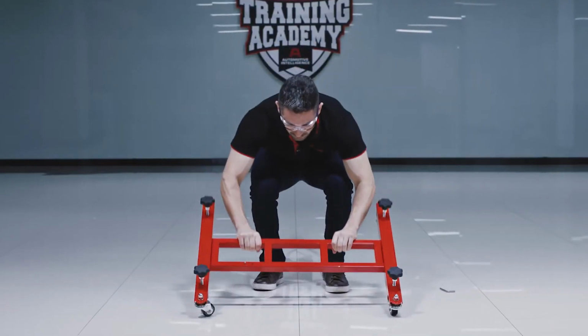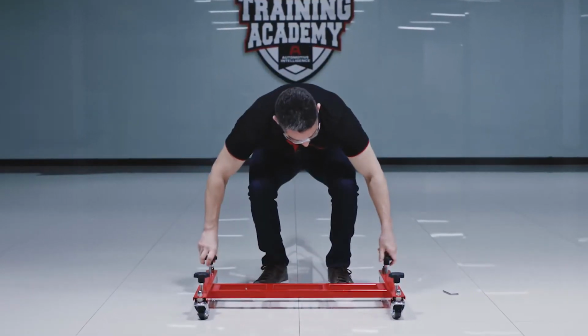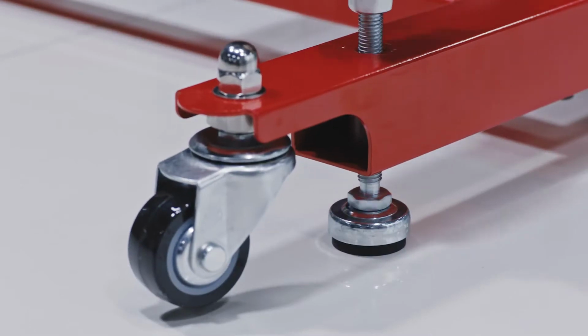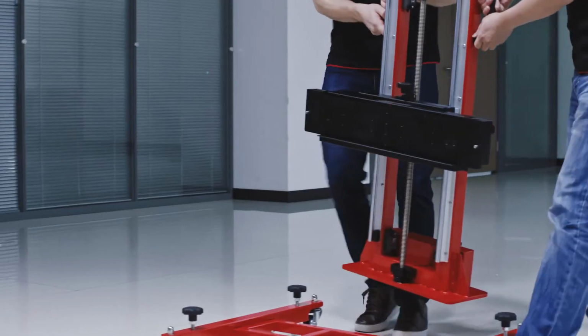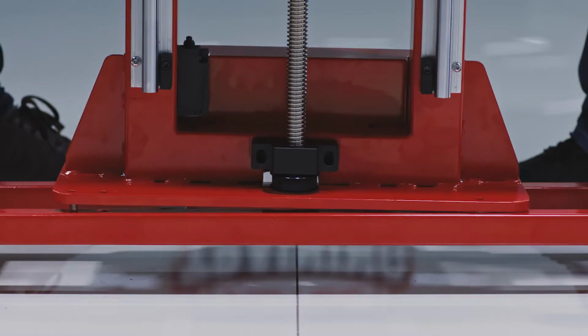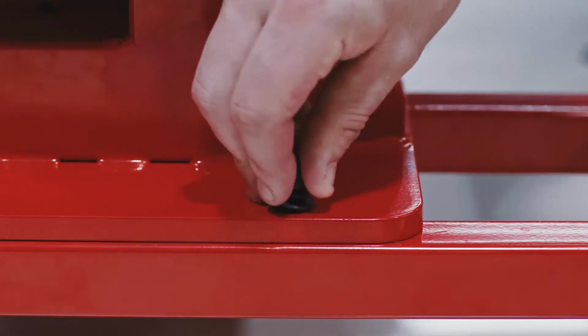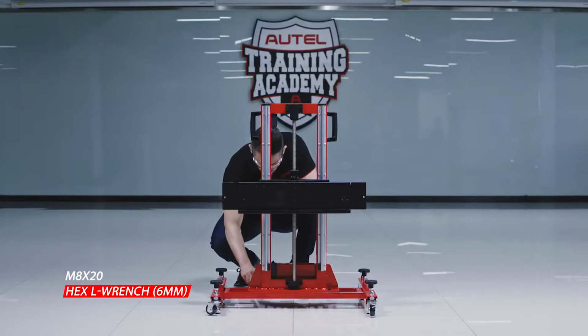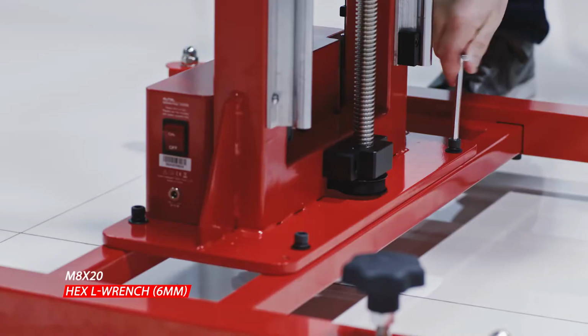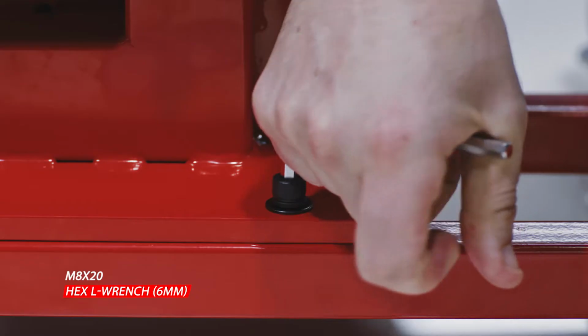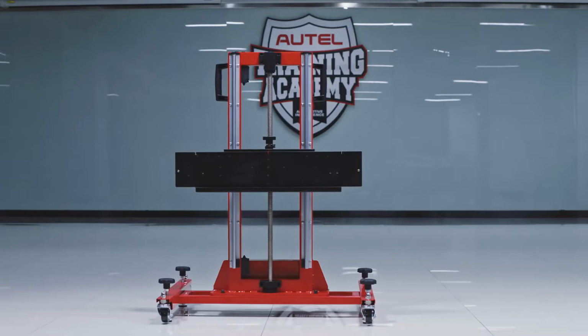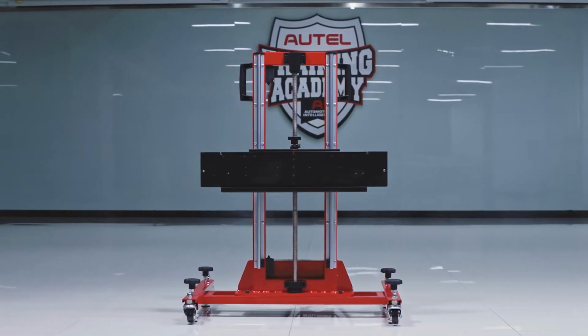Turn over the base. Rotate each of the 4 hand knobs clockwise to secure the base to the ground. Align each of the 4 screw holes on the lifter with those on the base. Position the bolt with washers. Tighten with the Hex L-wrench 6 mm and ensure the base and the lifter are firmly attached.